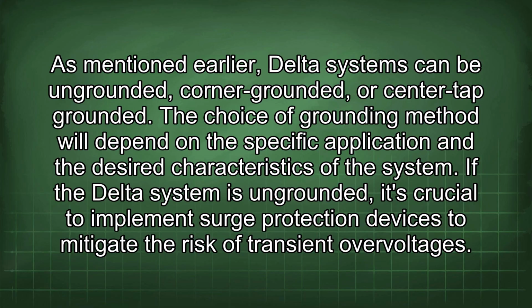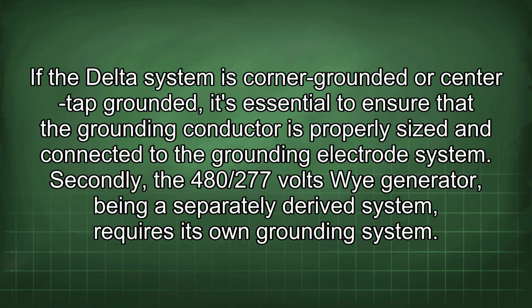If the delta system is ungrounded, it's crucial to implement surge protection devices to mitigate the risk of transient overvoltages. If the delta system is corner grounded or center tap grounded, it's essential to ensure that the grounding conductor is properly sized and connected to the grounding electrode system.